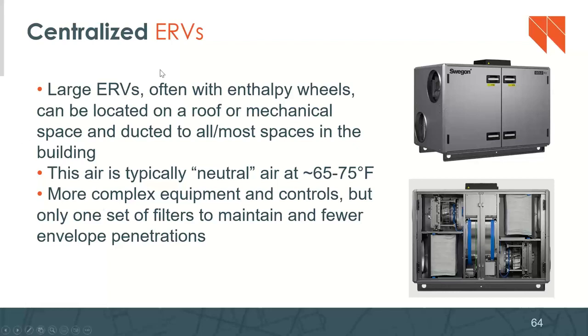And then, of course, the distribution of this ventilation air throughout the building, you know, the ducts. The amount of ducting that it takes to do this is large, and so there's a lot of room for duct leakage to happen because it's being ducted all throughout a multifamily building. And so even small amounts of duct leakage could sort of lead you not to get to those passive house levels of how much air we can measure being delivered and exhausted out of an individual apartment. So duct leakage becomes a big concern.